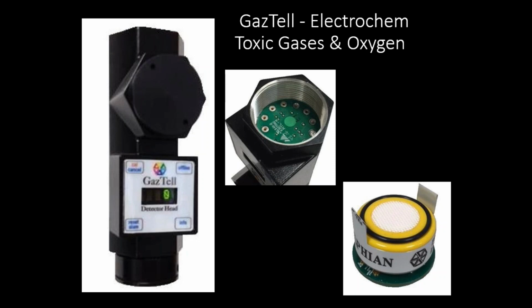If the sensor, such as hydrogen sulfide, has multiple scales, such as 0 to 25 ppm, 0 to 50 ppm, or 0 to 100 ppm, you can then go into the info menu, which again you can look in the manual and see how that works. You can go into the info menu and actually select the scale that you want to use with that particular electrochemical cell. We have 3 videos that we're going to be showing you today. One of them will be set up, and that will show you how the info menu works.